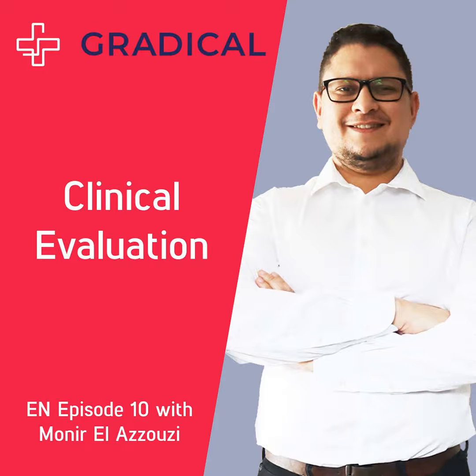Okay. So you would do that basically on a paper basis. You research the state of the art, you research literature for data for equivalent devices. So you're trying to fill data gaps that you do not want to test yourself from devices that already exist. Maybe your device is so novel, or you're doing something that you have not found in the literature, that you have to perform a clinical test.